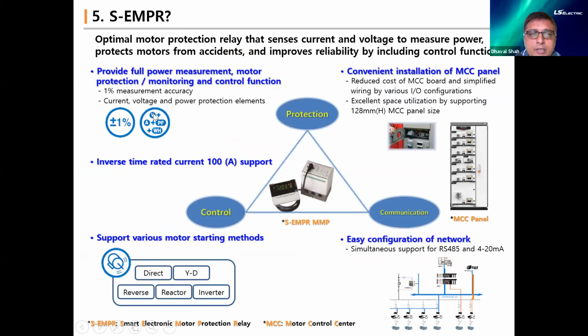So what do we get? We get 1% class accuracy, we get voltage monitoring, current monitoring, and power factor monitoring. Inverse time rated current is available. Controlling, you can control the starters: direct, star delta, reverse starter, and so on. Means any mode of operation is possible with these starting functions. Protection, of course, you will get all the protections of current, voltage, and power. And you can also have the communication through RS485.